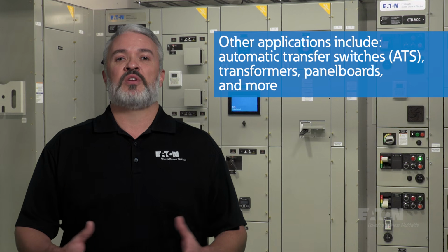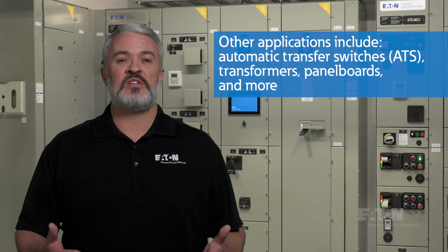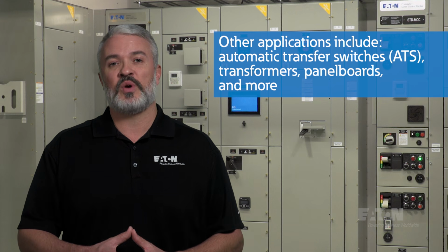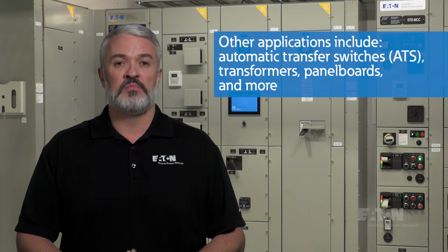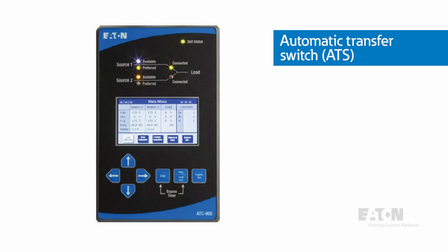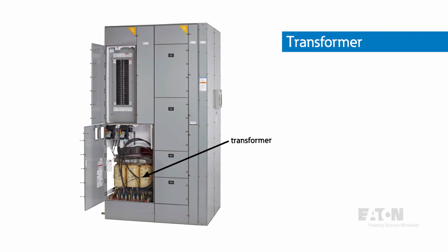There are other special applications that can be installed in an MCC, which include an automatic transfer switch or ATS, transformers, panel boards, and more. An ATS can be installed to control main tie or main tie main operations of power circuit breakers or contactors. 3-phase dry type distribution transformers can be installed in an MCC up to 45 kVA. They can be used to feed specific loads or a panel board that is also mounted within the same MCC.